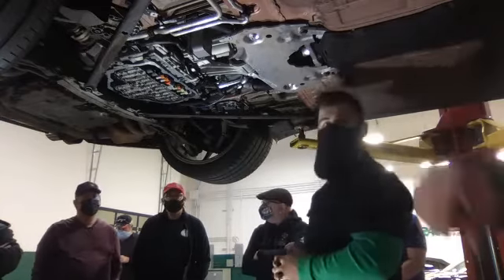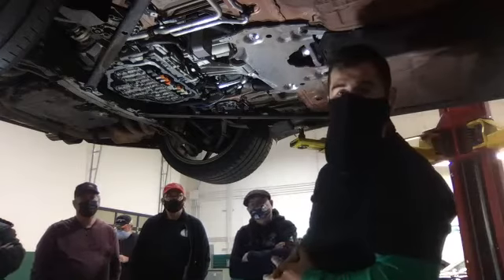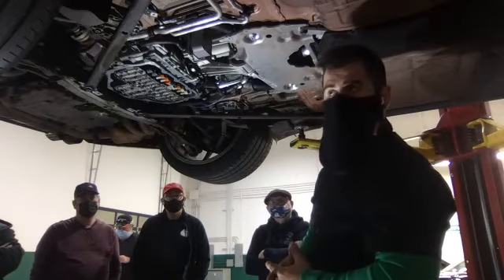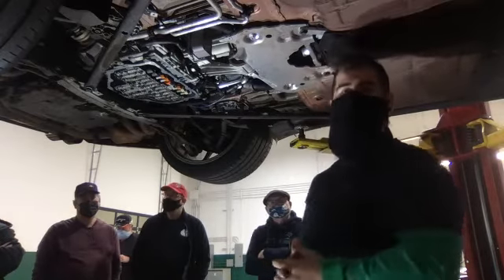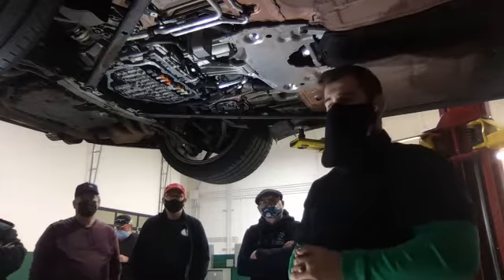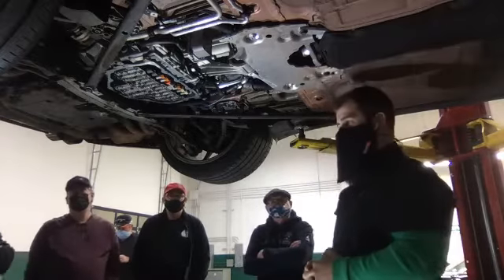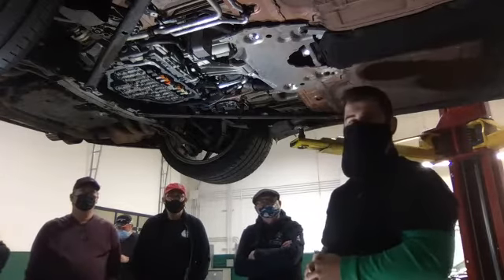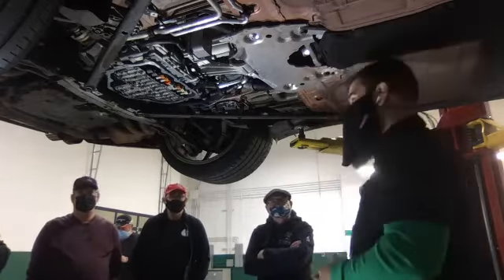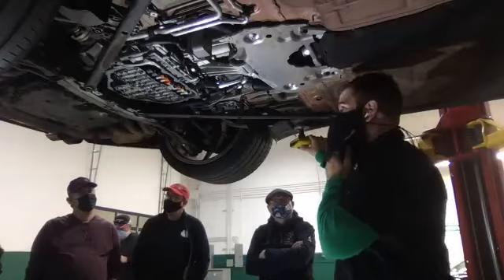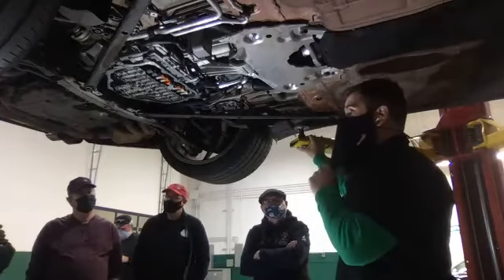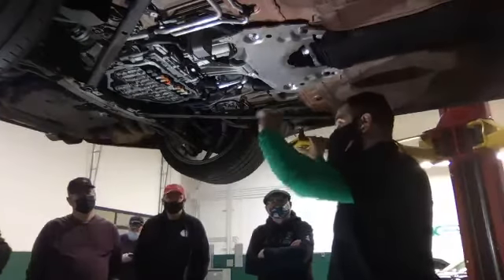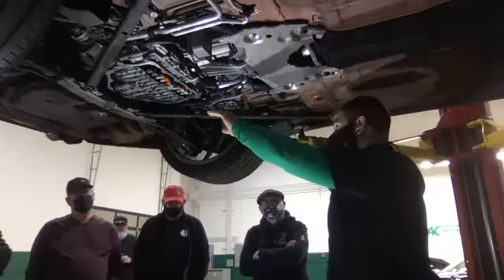Expanding on one of the online questions: does the scanner run the calibration process automatically? No, you have to tell it to. You have to go in there deliberately, and it asks you like three or four times, are you sure you want to do this? And you say yes. It wants to make sure you want to do it, because it runs through a whole process where it bleeds the valves again.